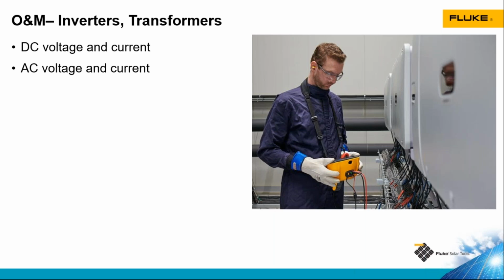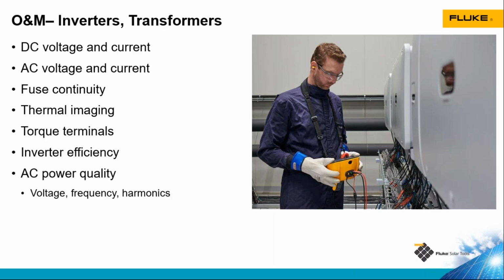Our inverters and transformers also need operations and maintenance. We can do AC and DC voltage and current testing. We can check our fuses to make sure that they haven't blown. We can do thermal imaging to look for both hot and cold conductors or terminals. We can do torque tests on our terminals. It's really important to make sure that they haven't loosened up over time. We can check inverter efficiency, making sure that it's converting DC to AC at the proper rate. And then we can do AC power quality testing, looking for variances in voltage, frequency. We can look for harmonics. We can also look for those transient voltage spikes if we have a power quality analyzer that is capable of measuring those voltage spikes.